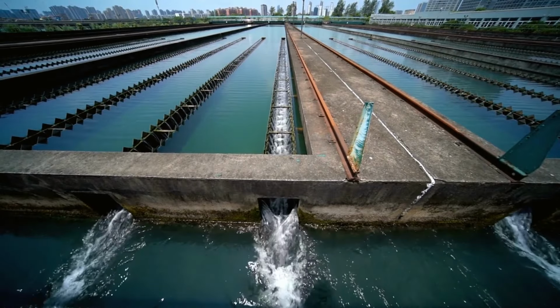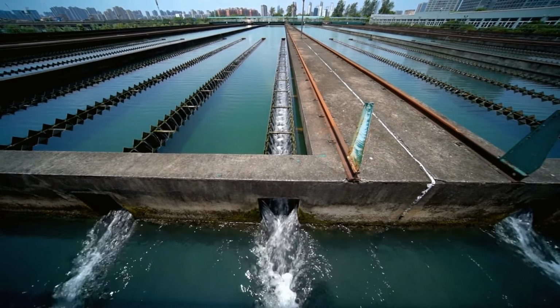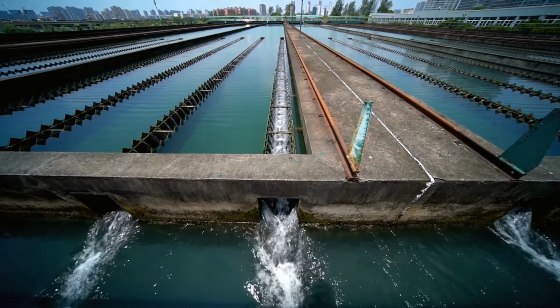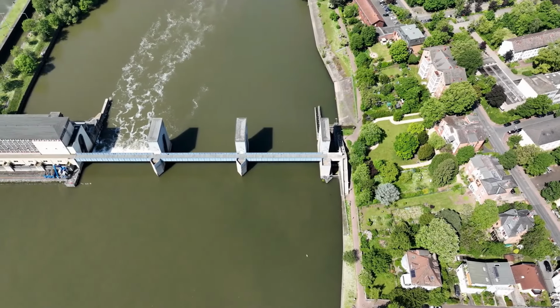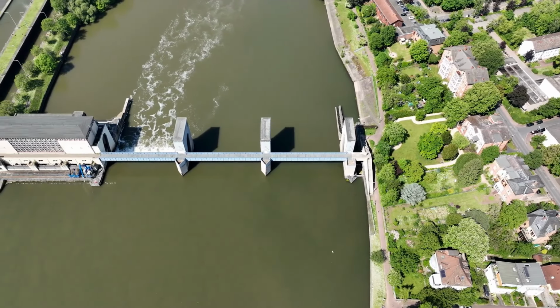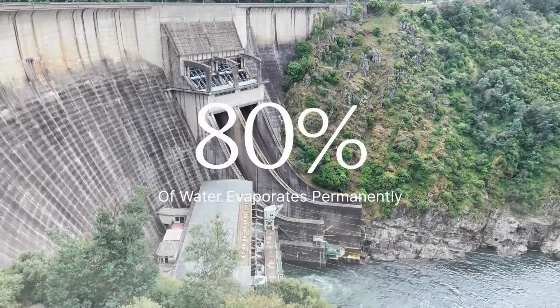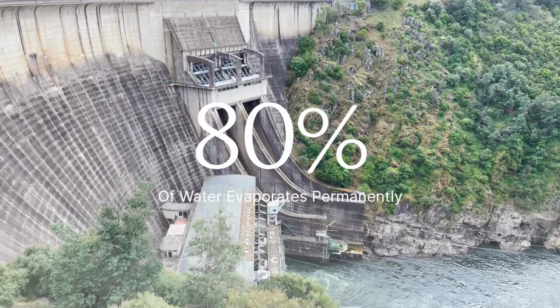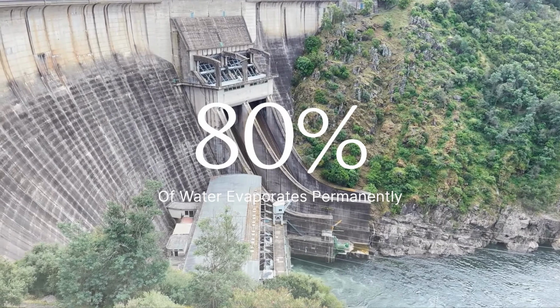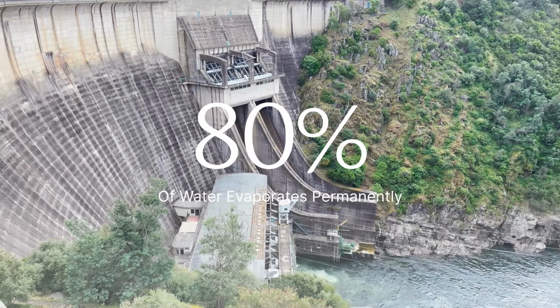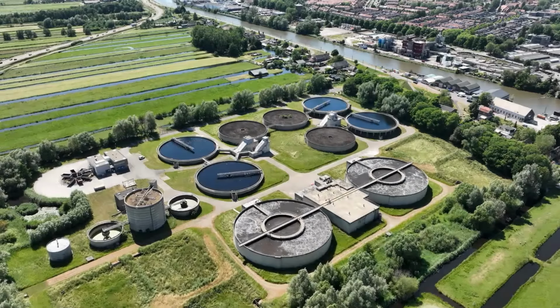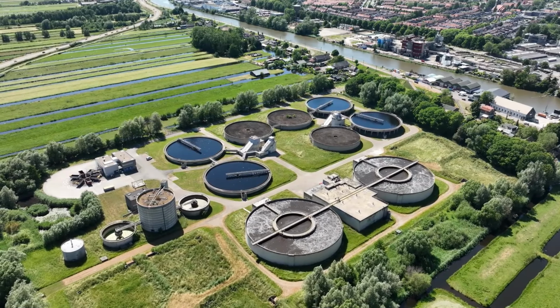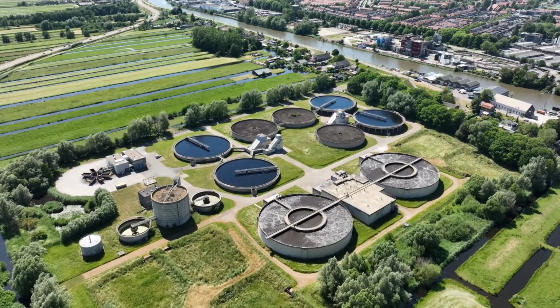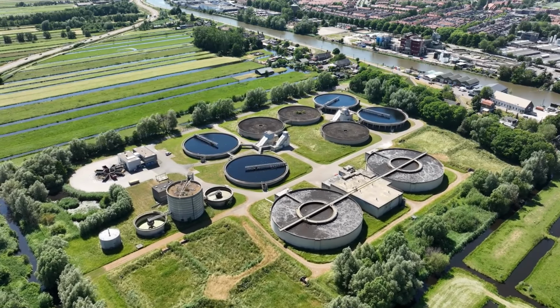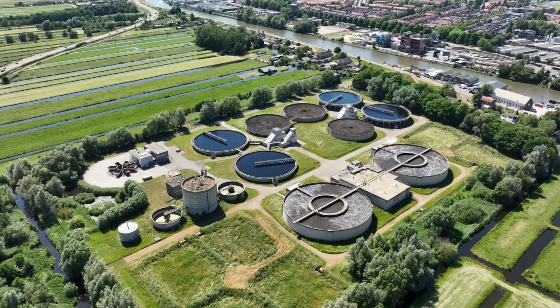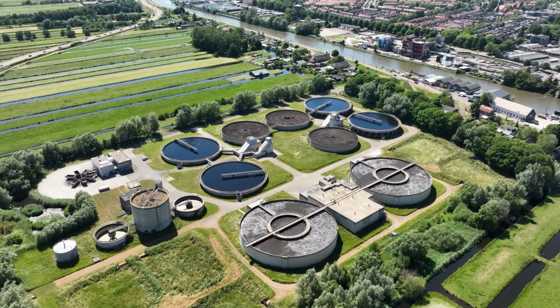Blowdown water goes to municipal sewer, flows to a treatment plant, gets processed, and then is usually returned to the river or aquifer. Hydrologists call this non-consumptive use because that water comes back to the watershed. So the math is 80% of the water evaporates and leaves the watershed permanently, 20% returns via the treatment plant, so the total consumptive loss is 80%. Except that's not quite always true. If the sewer system drains water out of the local basin and it flows to a treatment plant that discharges it to a different river system or to the ocean, then from the perspective of your local aquifer, you have consumed everything you withdrew, and that blowdown doesn't come back.